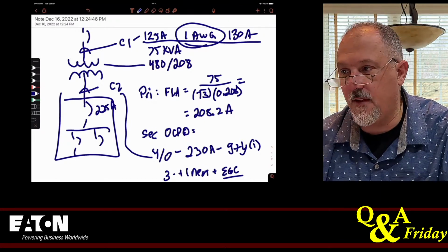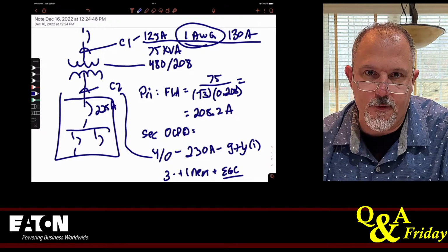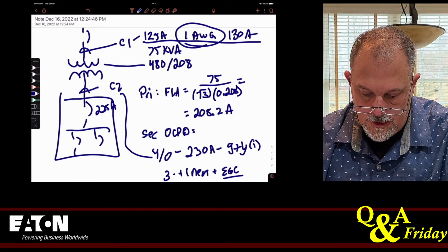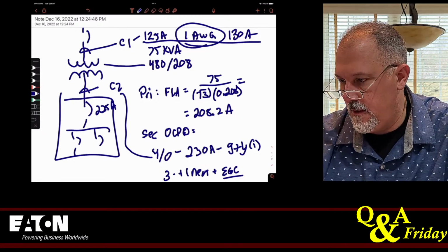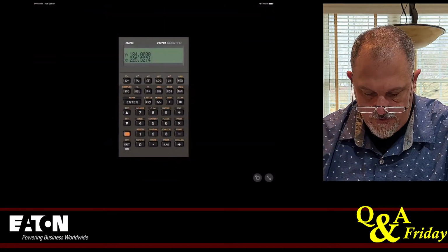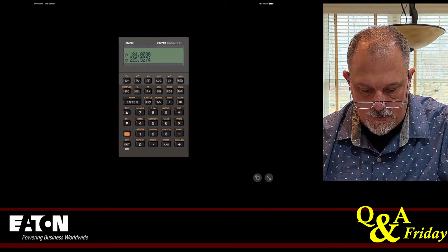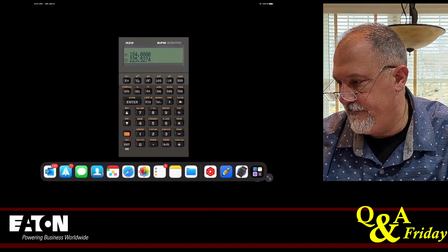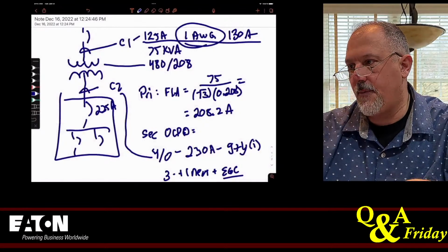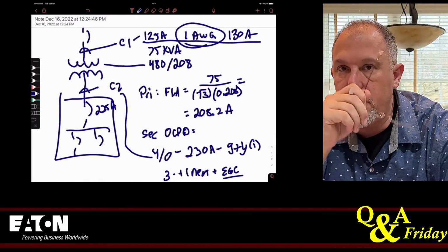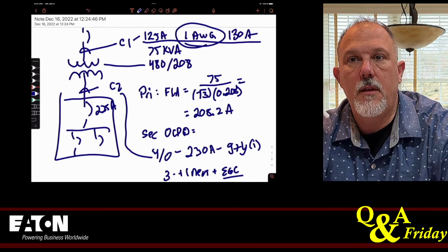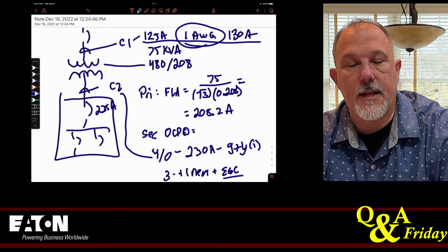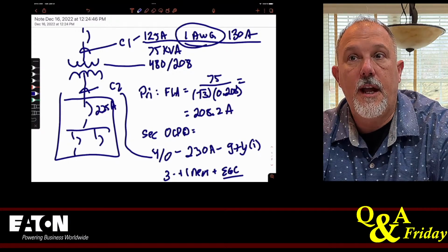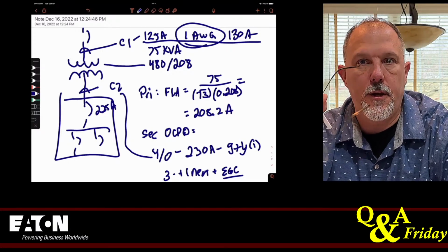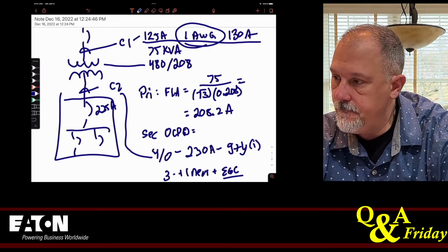And that might even give you some breathing room in case you have to put a larger breaker in for whatever reason. And if I went to 250%, what was 250%? 225 amps. If I had to do 225 amps, I'd probably put a 4/0 on the primary. So a 4/0 and a 4/0. But I'd probably go with 130 amps. So once you pick the overcurrent protection for primary and secondary that gets you what you need, you'll pick your breakers based upon the equipment you can put upstream and the equipment that you're going to feed.